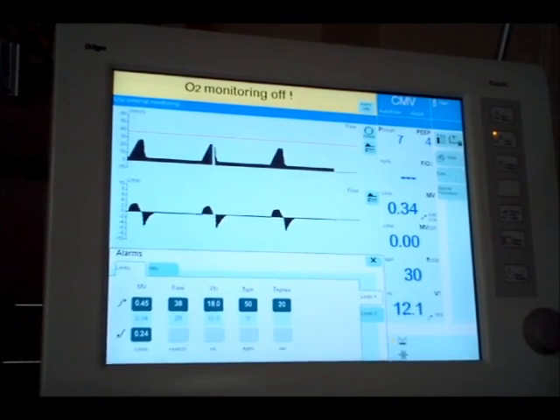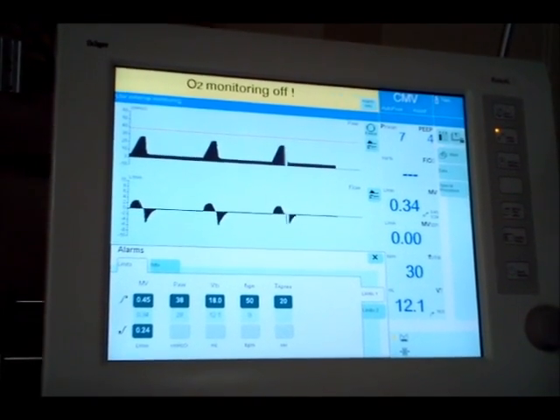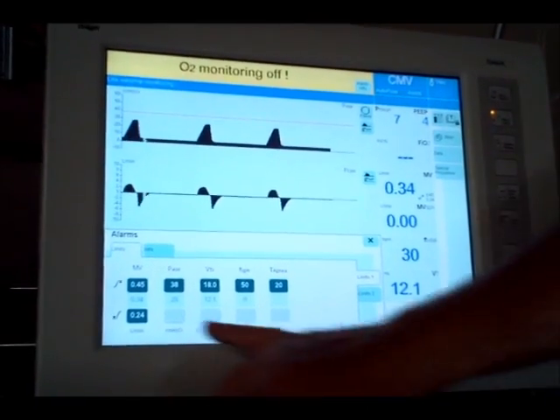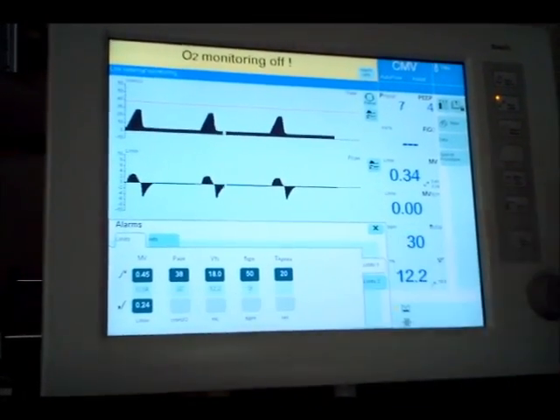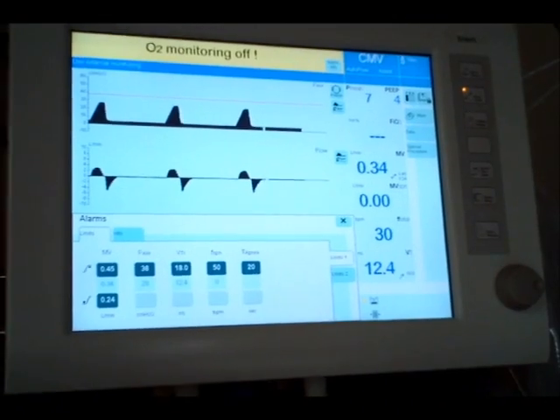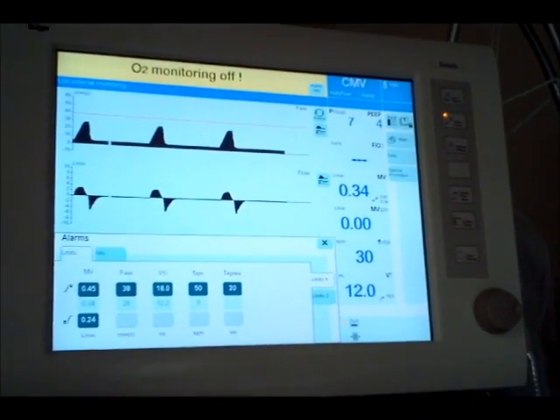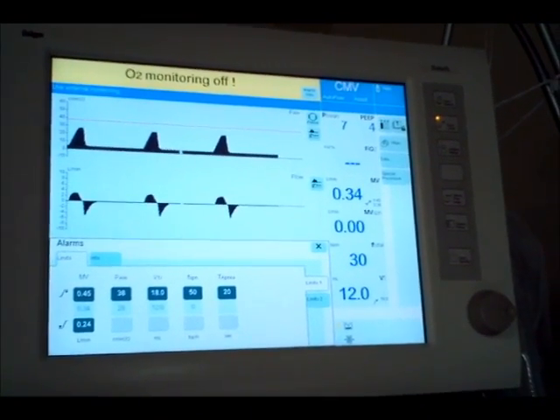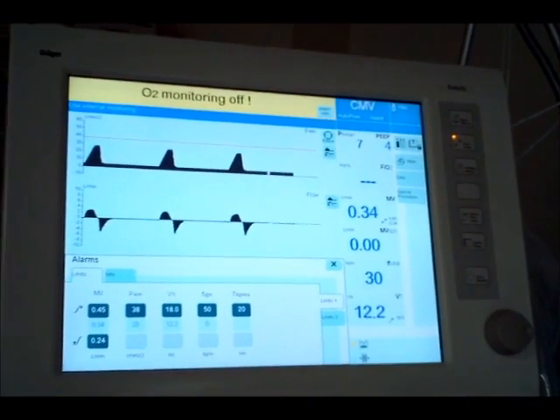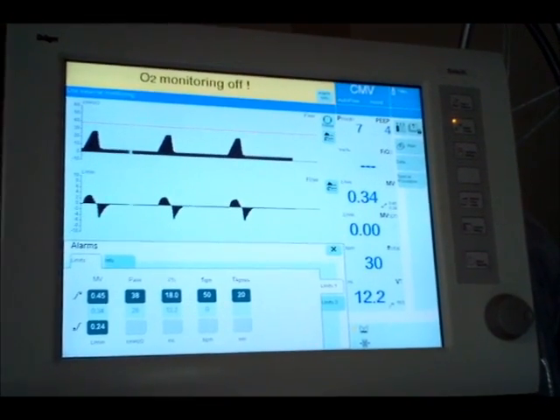Your low minute volume alarm hopefully will go off fairly quickly. I guess something to point out is this is exhaled minute volume, okay? So it's volume coming back from the patient. So what would happen is the ventilator sends the gas to the patient, it doesn't come back, then that low minute volume alarm should go off fairly quickly.